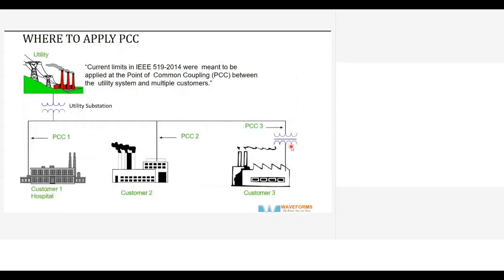This is an important thing that you have to understand: the PCC, the point of common coupling. The point of common coupling is the point where power from the substation is distributed to the other plants, and the measurement also is done at that point in the industry. This is where the TDD is calculated.